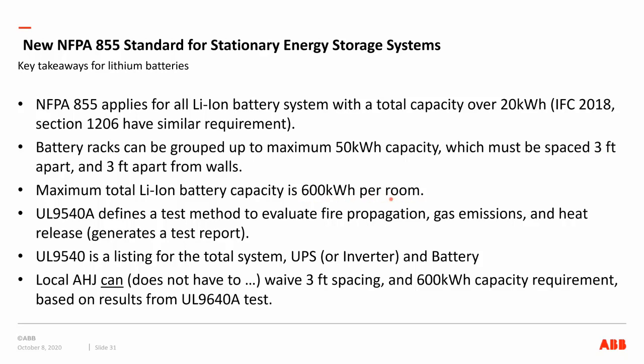So lithium ion is obviously still lighter, but the footprint is now suddenly bigger than the VLA. So that benefit went away with this. But there are some ways around that. And everybody's still learning, so there are no guarantees, and I'll get to that also. And actually I should say the International Fire Code 2018 does not reference 855, but it has very similar requirements about the 50 kilowatt hours and 3 feet spacing between the cabinets, and the 600 kilowatt hour maximum.